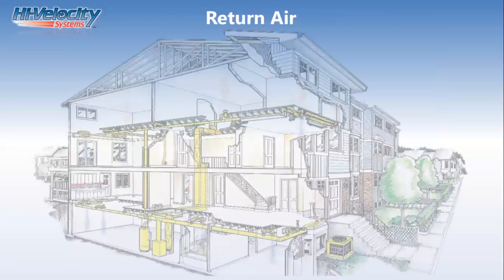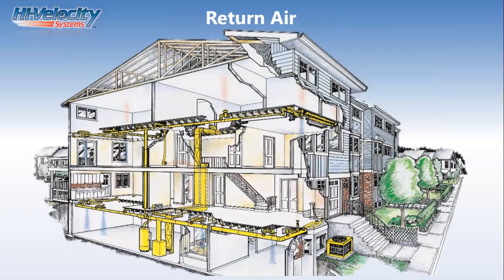When it comes to return air, we still need return air duct, but because our system's not reliant on the return air to mix and move, we do not require return air in every single room throughout the home. Most of the contractors that are our customers will elect to go with a central return air per floor, which is more than adequate to get the energy back to the air handler it requires to create the heated, cooled BTUs at the power plant and deliver them throughout that space. You can put return air in every single room with a high velocity system, although it is not required. The central return air is most commonly practiced, and we would insist on some sort of a 1/2-inch undercut under most doors for airflow to escape out of a room if that door does close.